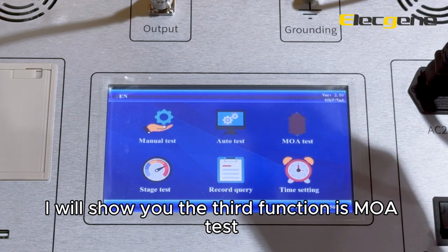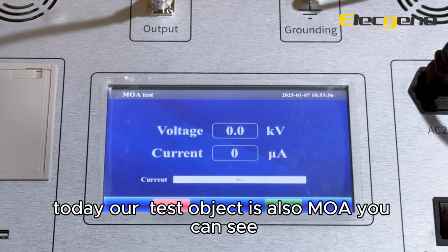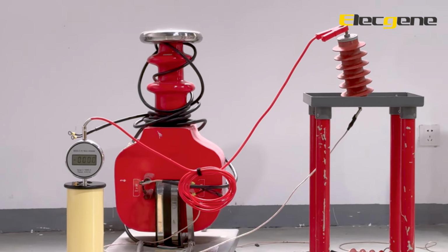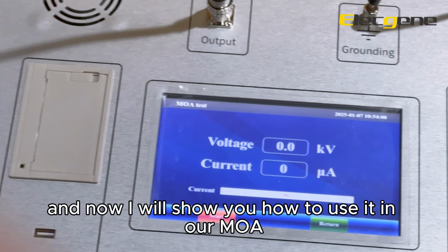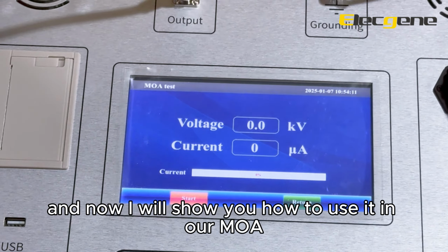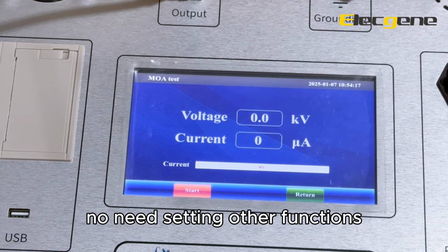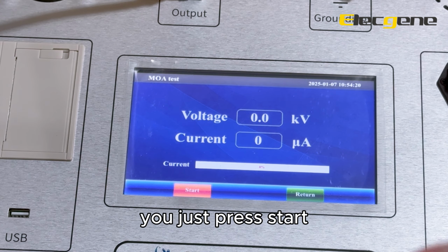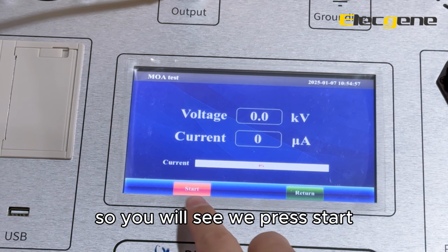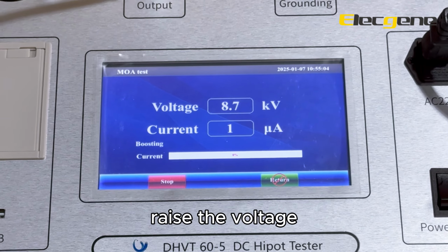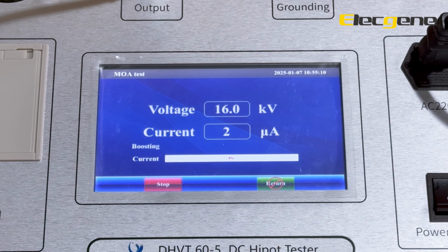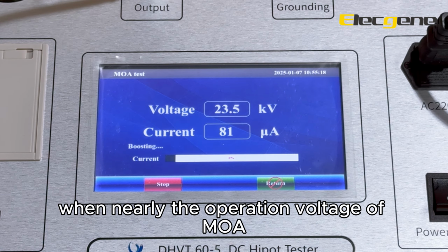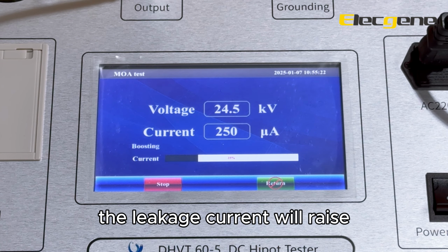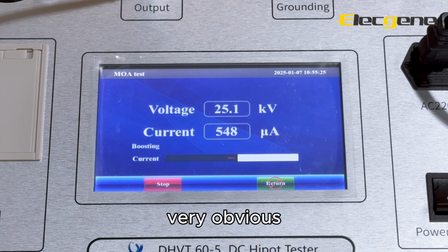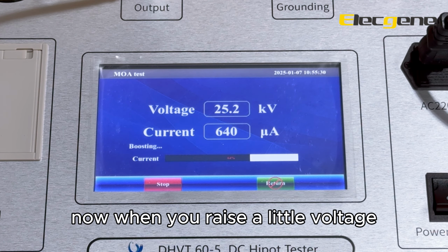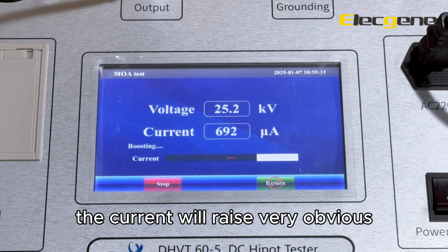And I will show you the third function, which is the MOA test. Today our test object is also a MOA. You can see it's also a MOA. And now I will show you how to use our MOA test function. So in this screen, no need to set other functions. You just press start. So you will see we press start, and it will automatically raise the voltage, so you can pay attention to the current. When nearly at the operation voltage of the MOA, the leakage current will rise, very obvious. So you will see, now when you raise the voltage a little, the current will rise.